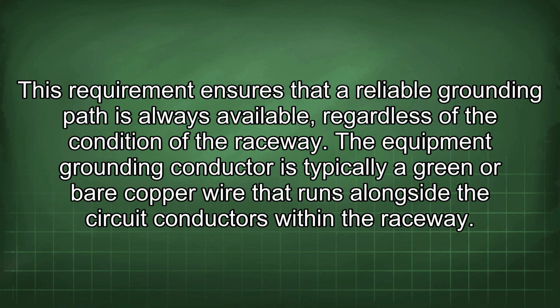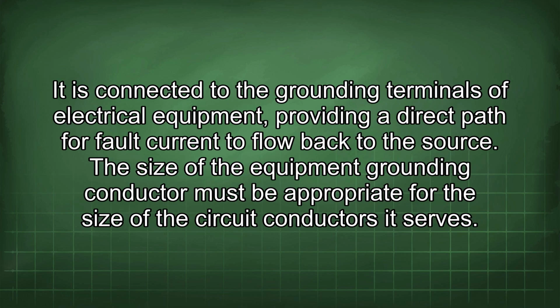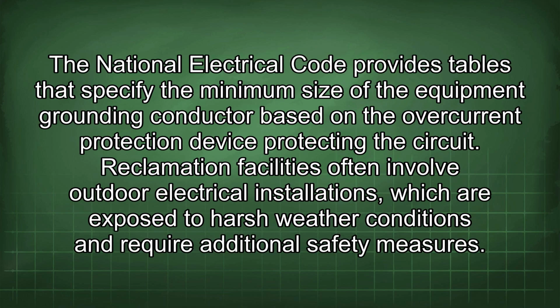The equipment grounding conductor is typically a green or bare copper wire that runs alongside the circuit conductors within the raceway. It is connected to the grounding terminals of electrical equipment, providing a direct path for fault current to flow back to the source. The size of the equipment grounding conductor must be appropriate for the size of the circuit conductors it serves. The National Electrical Code provides tables that specify the minimum size of the equipment grounding conductor based on the overcurrent protection device protecting the circuit.